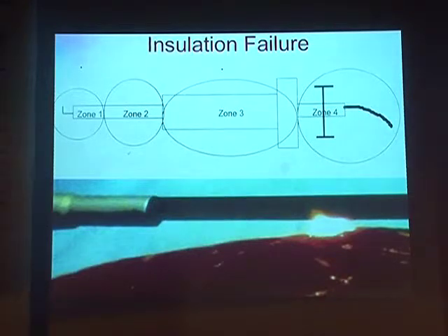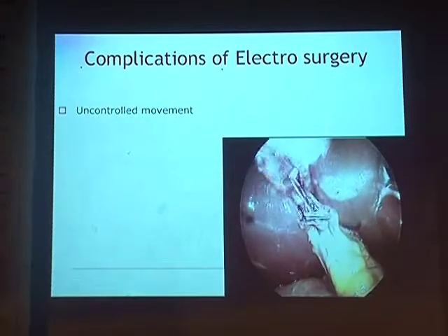But zone 4 failure means the surgeon is electrocuted. If there is any failure in zone 4, the surgeon can get electrocuted. So we must always check this zone of all the laparoscopic instruments which we use that deliver energy. They should not have any insulation failures. Sometimes this kind of problem may appear.